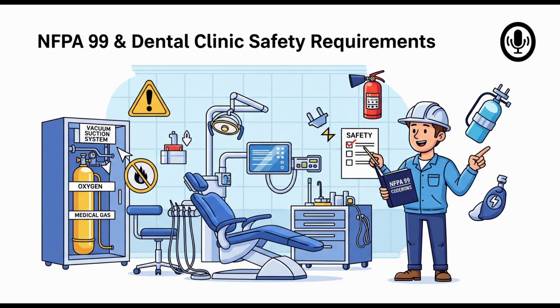Section 5.3.3.6.13 clearly states that the emergency electrical service for Category 3 medical air systems must conform to Section 6.6 and NFPA 70. Okay, so the air compressor needs backup power. Yes. And similarly, Section 5.3.9.4 requires that the electrical power for the Category 3 warning systems, those alarm panels, must also comply with the applicable parts of Section 6.6 for Category 3 spaces. So the alarms need backup power too. Even if the rest of the clinic goes dark, the air compressor and the gas alarms need to stay on. That's what those sections mandate.